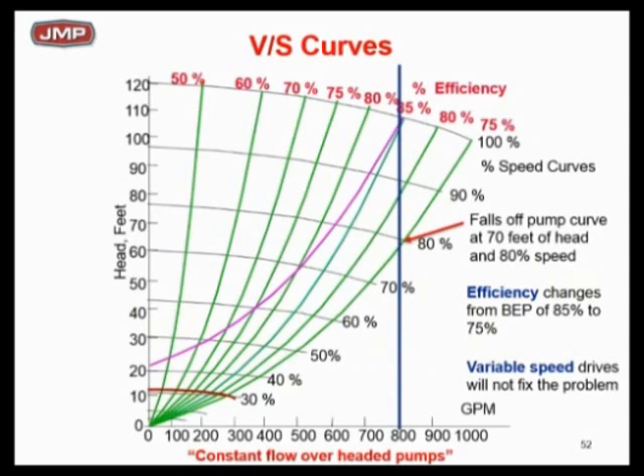Where is 70 feet of head going to land when your variable speed drive starts slowing the pump down? At 100% speed you don't need 110 feet — you only need 70 feet. So the VFD slows to 90%, then 80%, but look at that last green curve, which is at 75 feet. If you get below 80% pump speed, if you get below 70 feet of head, the pump falls off the curve — the pump dies, cavitation occurs. You've got a big problem. How do you fix it? You have to go throttle the pump discharge valve.